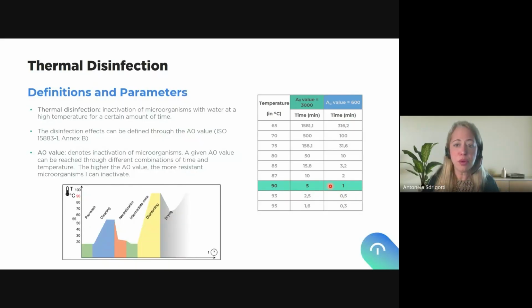Just as another example, if my machine is not working at 90, it's working at 80, you see I need 10 minutes, but I will reach the same level of disinfection, of inactivation of microorganisms and cells. Okay? The same with A0 value 3000, which nowadays is mostly used because it adds an extra guarantee, an extra safety of disinfection, in just 5 minutes at 90 degrees. So just showing you the most regular or most used combinations of parameters for thermal disinfection nowadays. Okay, the higher the A0 value, the more microorganisms I'm able to inactivate, or the more resistant microorganisms I can inactivate.